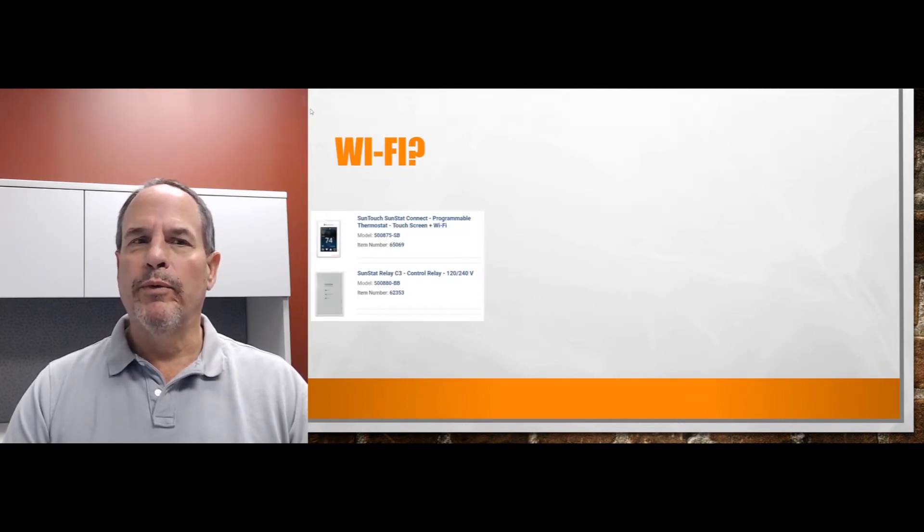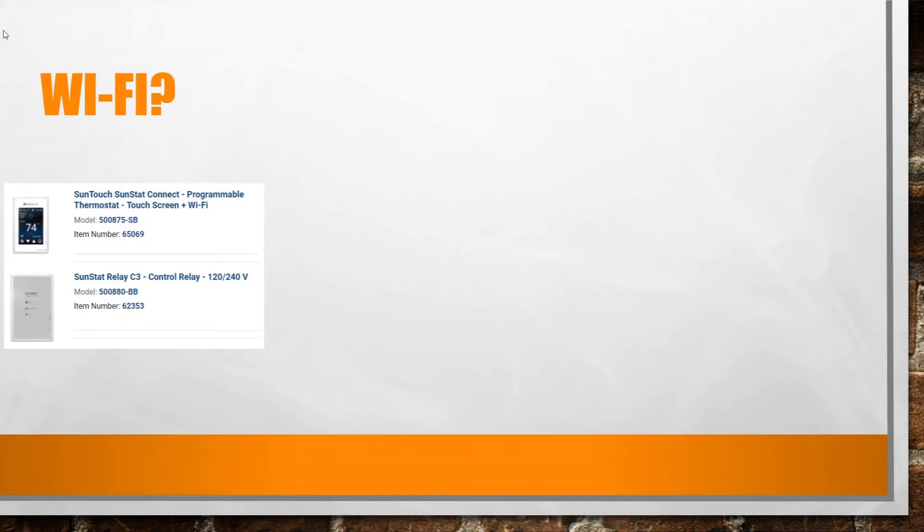The most common one that we use is a SunTouch SunStat thermostat - say that real fast - and that allows you to work up to a 15 amp 240 volt system regardless of whether it's an air handler, a floor heating element, or a baseboard heater.